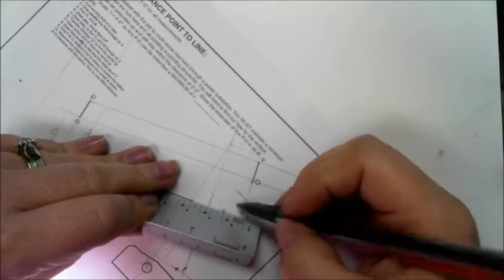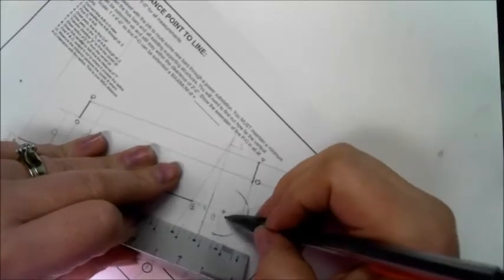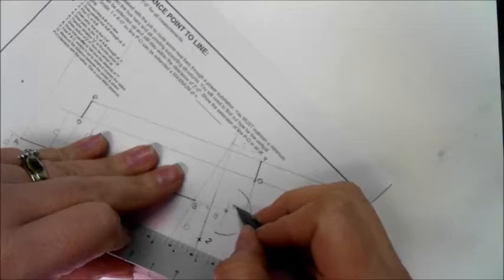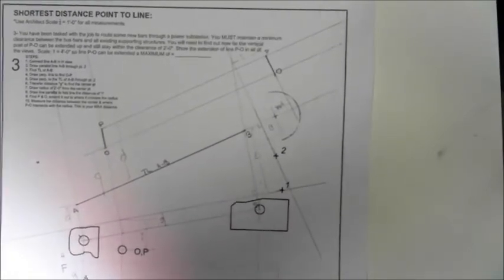So you find the 1 foot mark here, and then you have to figure out how many inches, and that's your max clearance. Whatever that distance is from here to there, that's your max. You take your scale and lay it on there, and that's going to tell you the maximum distance that you can put in the tower or extended tower, whatever you need to do, without hitting one of these wires and electrocuting yourself or somebody else.